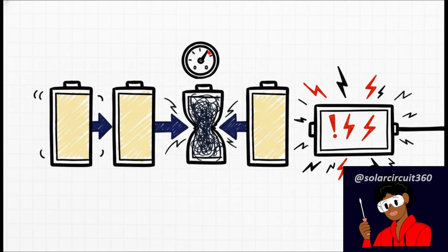What happens next? The healthy batteries are forced to work overtime, shoving current through that weak link. That weak battery suffers a brutal voltage collapse, and it literally drags the total system voltage down with it until, boom, your inverter trips on a low voltage alarm. And the craziest part? 3 out of your 4 batteries might be perfectly fine.